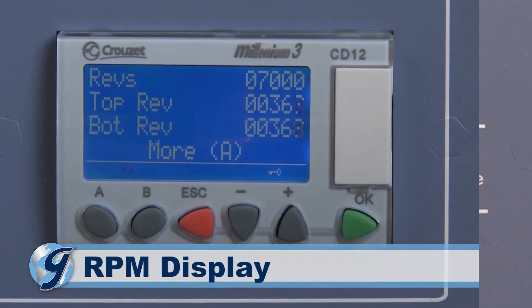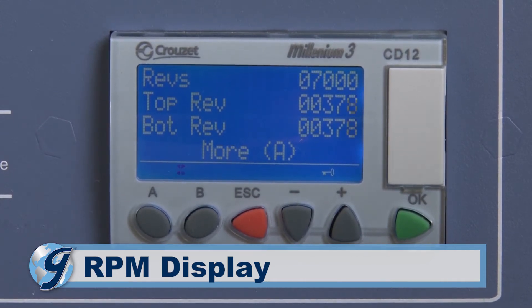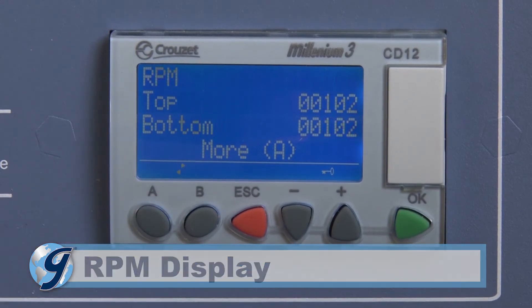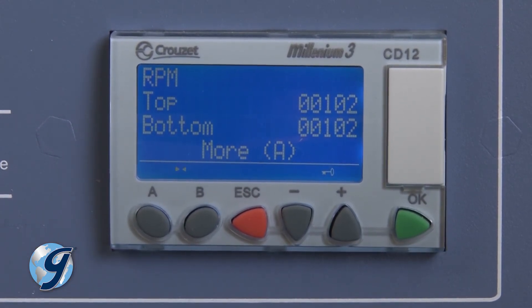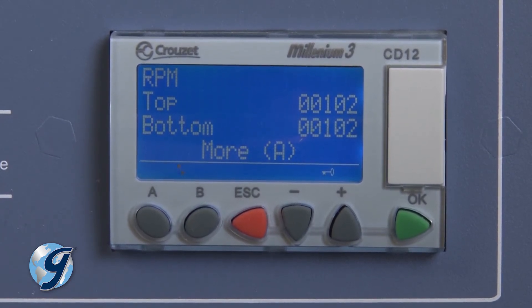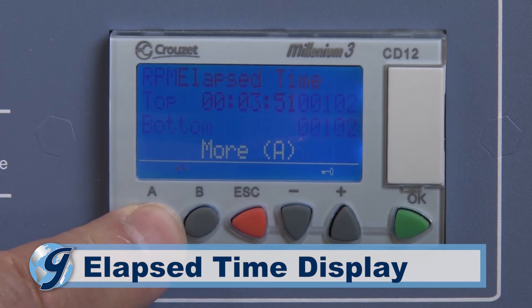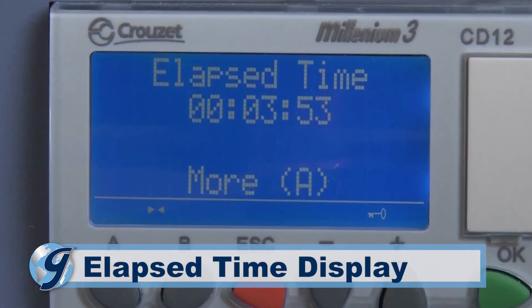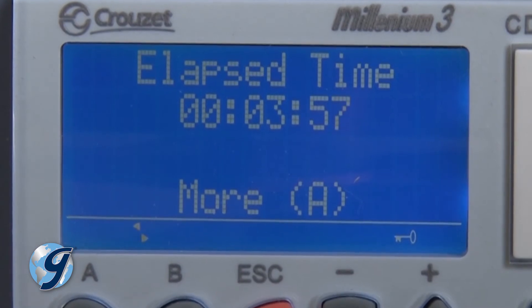To view the revolutions per minute during testing, from either the time mode or the revolution mode screen, press A. RPMs are counted during a full one minute increment and are updated every minute. To view the elapsed time display during testing, press A while the display is in the RPM mode. The elapsed test time is displayed and is updated every second.